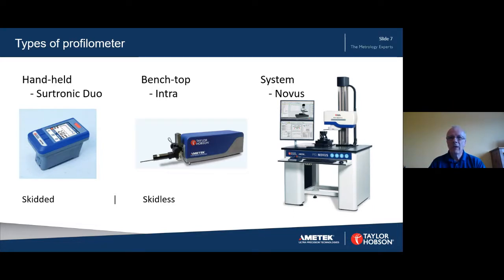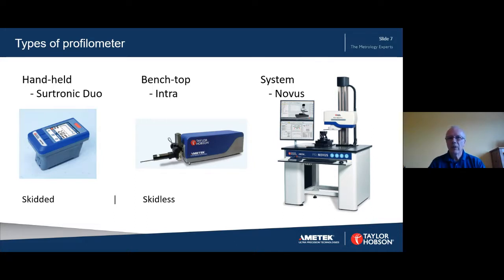The Surtronic Duo is an example of a handheld skidded instrument. This particular instrument is highly versatile as it can be split into two parts, allowing the small traverse and data acquisition unit to be located into small places. The Intra and Novus are both examples of skidless systems. The Intra can be used with a range of accessories that facilitate specific measurements, for example a special fixture for the measurement of ball bearings. The Novus is a floor mounted measuring system, which requires the component to be brought to the system for measurement rather than taking the instrument to the component.